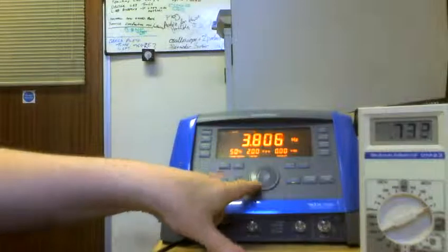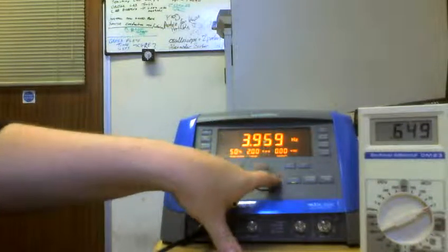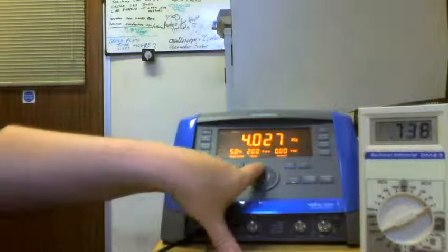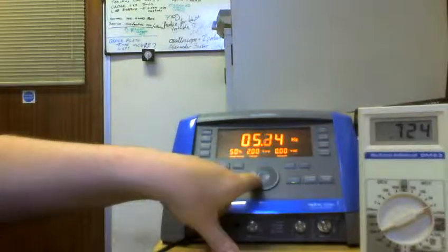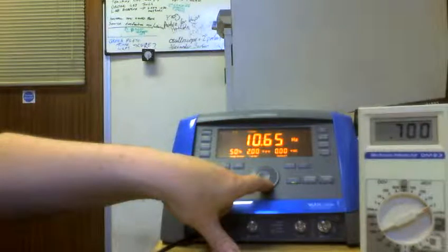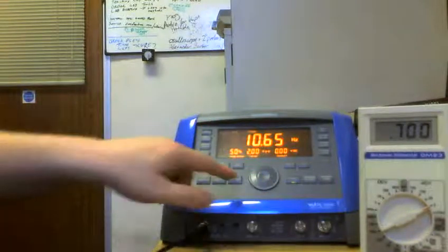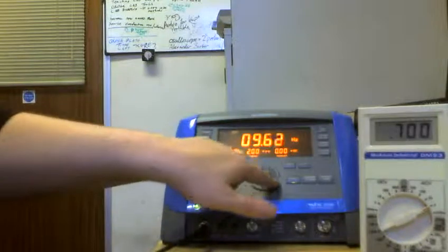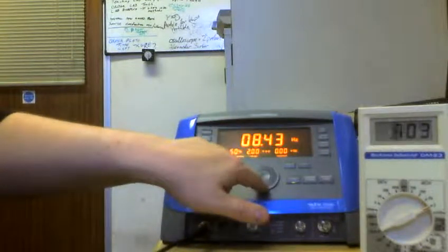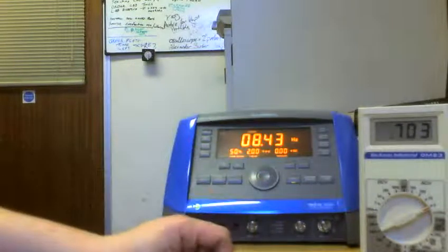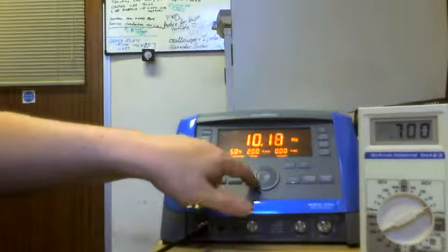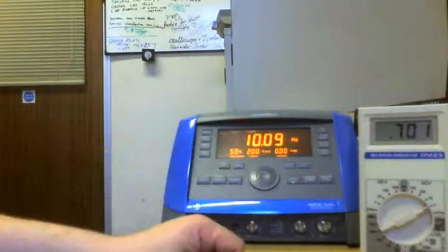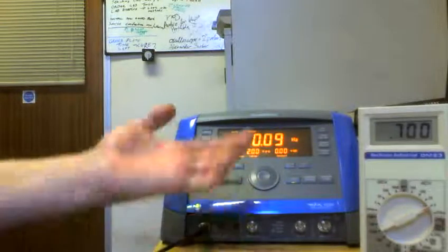Where it actually starts measuring, well, let's increase this. It's up to 4 hertz, still fluctuating, 5, 10 hertz roughly. Yeah, close. Roughly around 10 hertz. And we slowly reduce this down. There we go, it's starting to flicker about again. So roughly around 10 hertz is where you can start taking your AC measurements using the Beckman. And let's take a look at the other end.